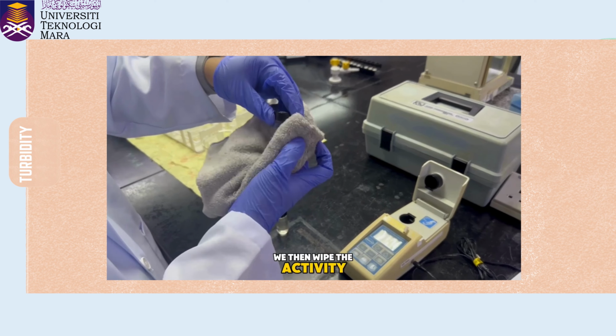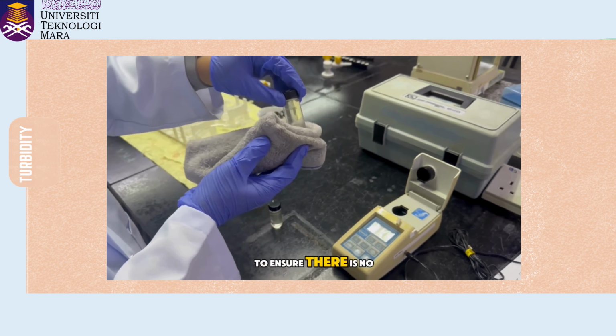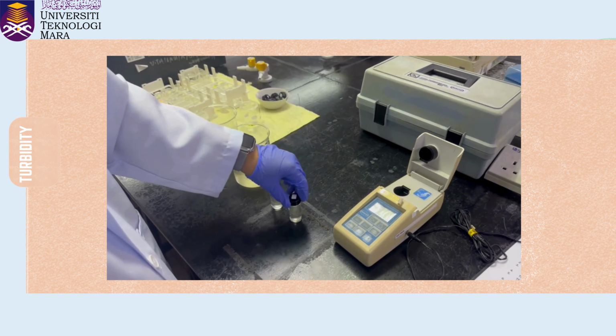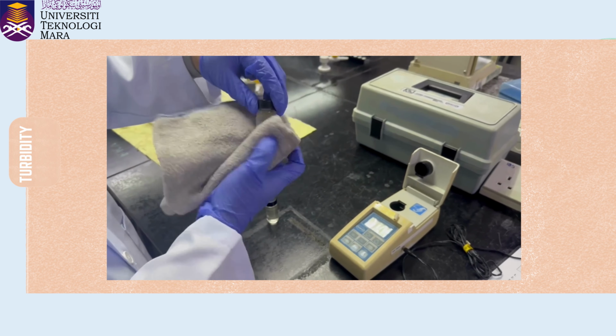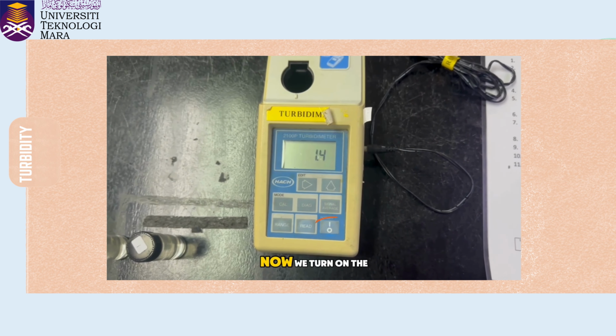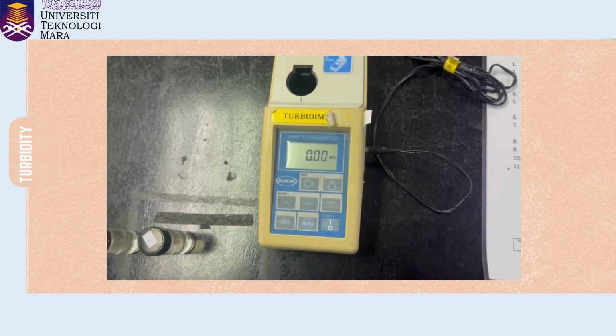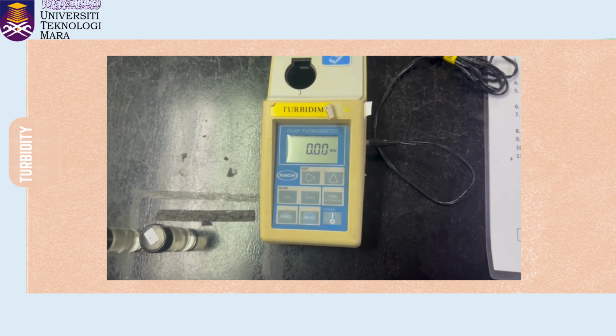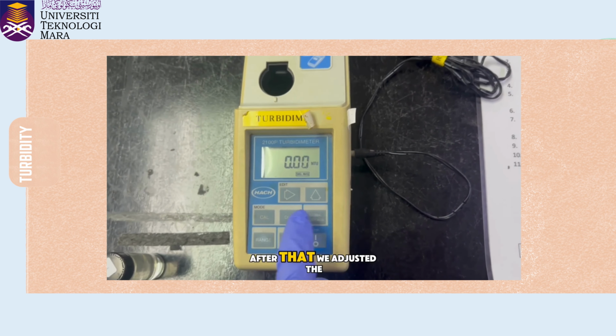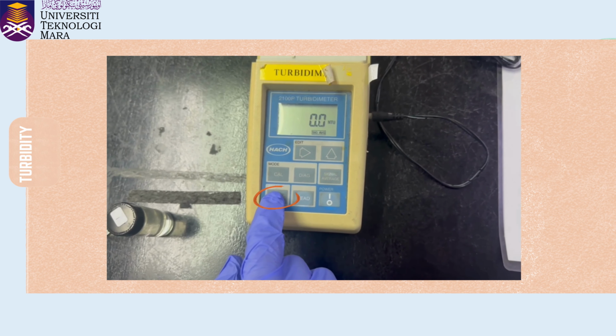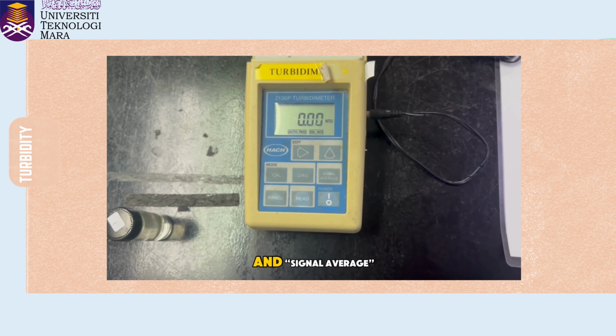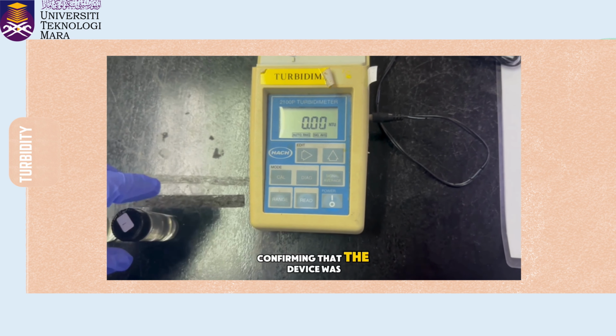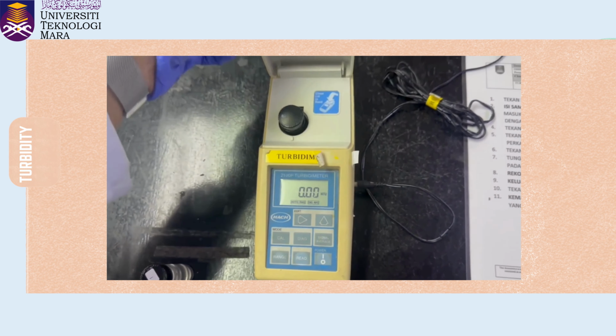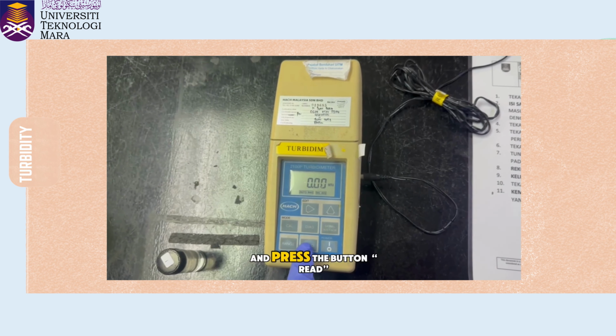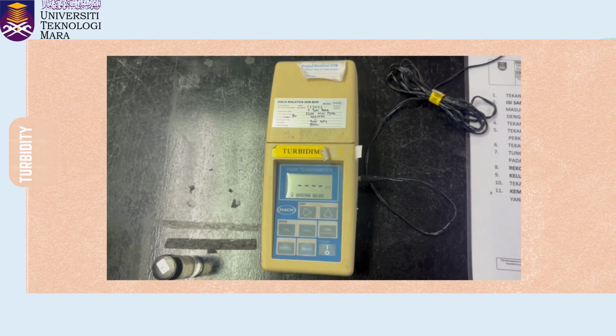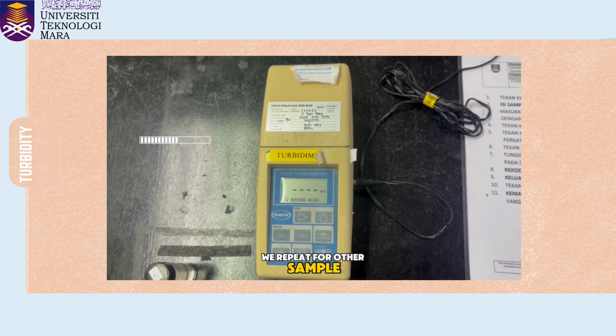We then wipe the turbidity meter cell with a towel to ensure there is no dirt or fingerprints. Now we turn on the turbidity meter and press the signal average button. After that, we adjusted the range setting until the screen displayed auto range and signal average, confirming that the device was ready for measurement. We inserted the turbidity meter cell and pressed the read button. After we get the value, we repeat for the other sample.